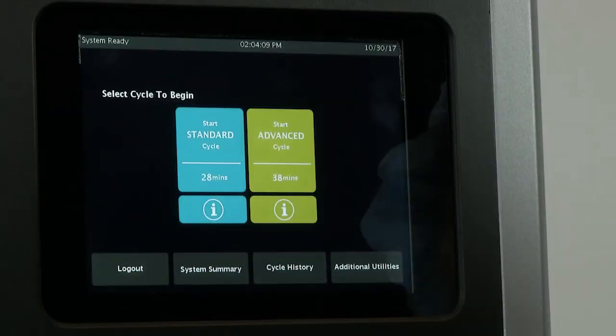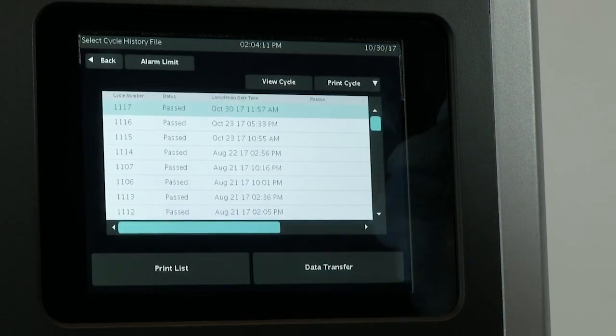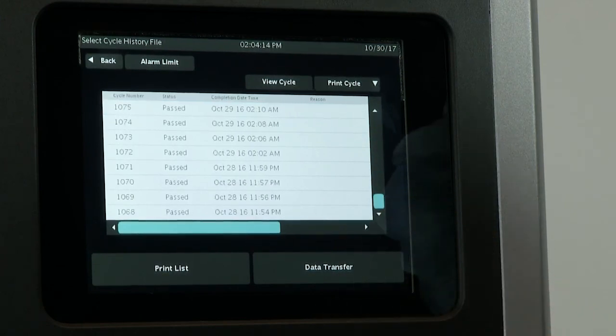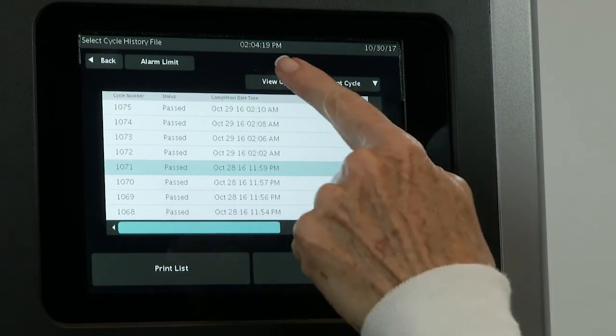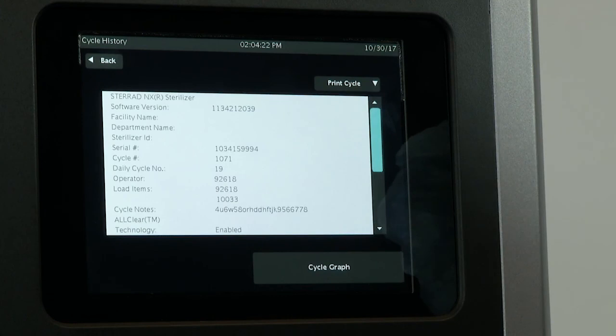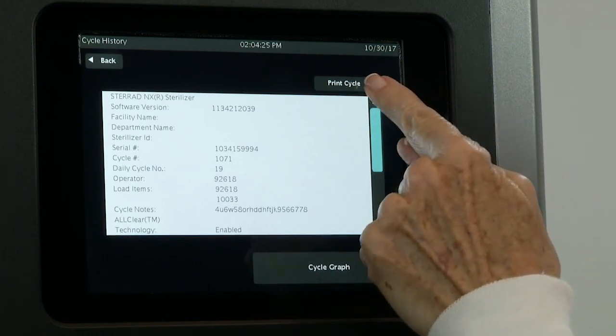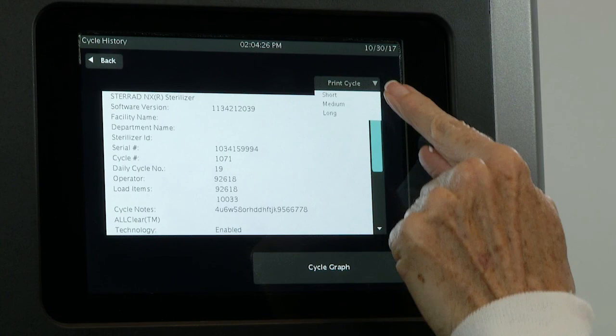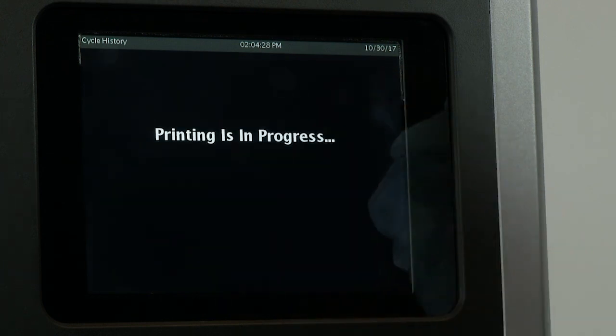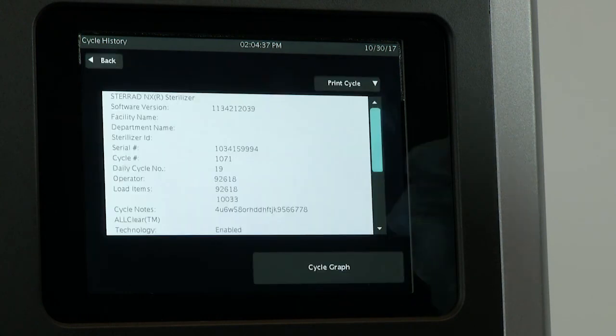Let's look at what's in the utility screen. Cycle history files contain very detailed information about each sterilization cycle. The files include identifying information about the operator, load, time, date, cycle duration information, stage-by-stage data from the sensors and controls, and related technical items. Information is extracted from the cycle history file to produce the short format report, medium format report, and the long format report. The cycle history file contains information that is vital to a healthcare facility's record-keeping and traceability procedures. The sterilizer's memory holds data from the last 50 cycles.